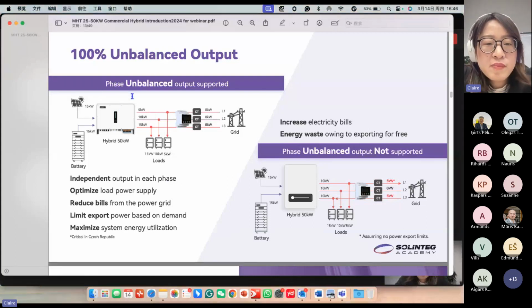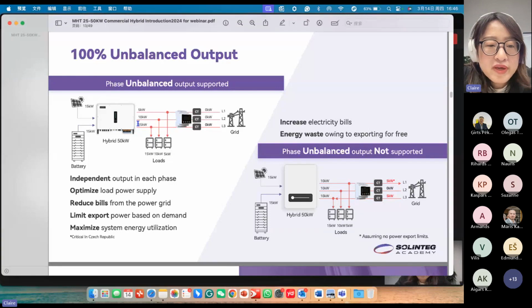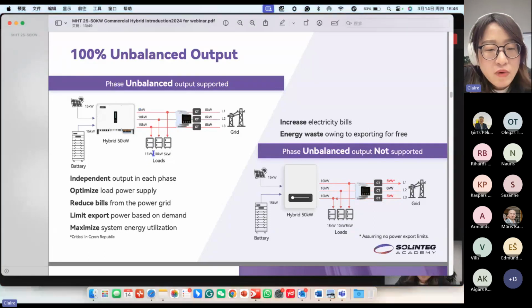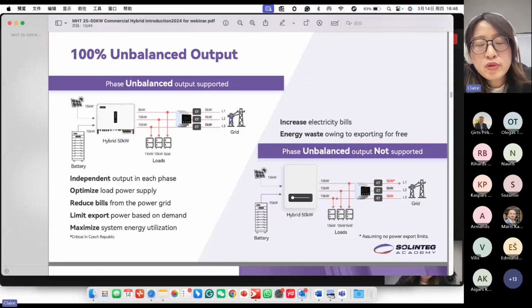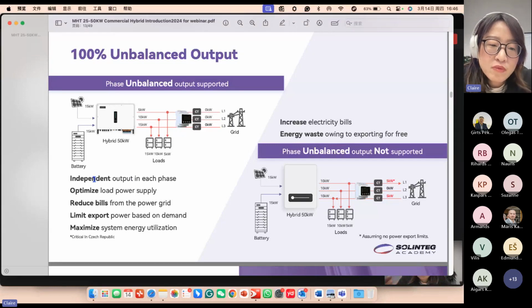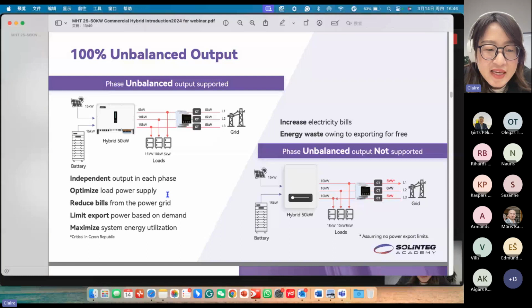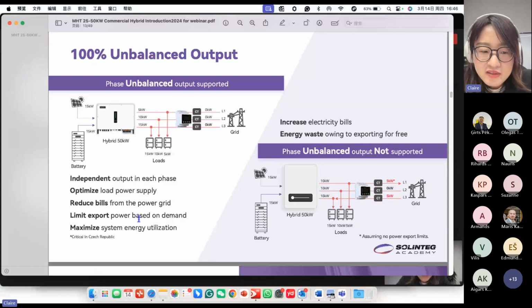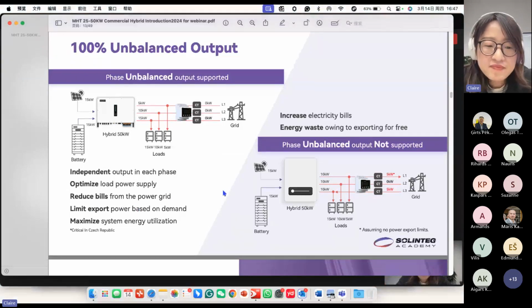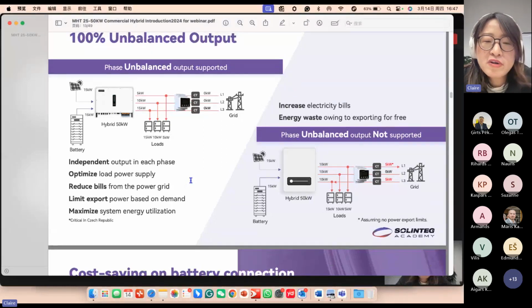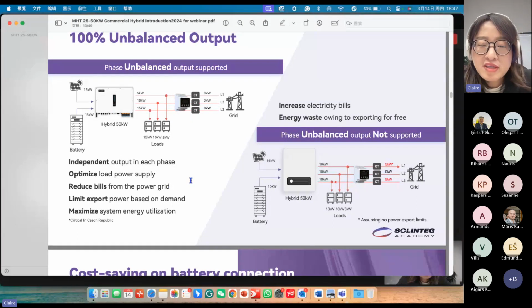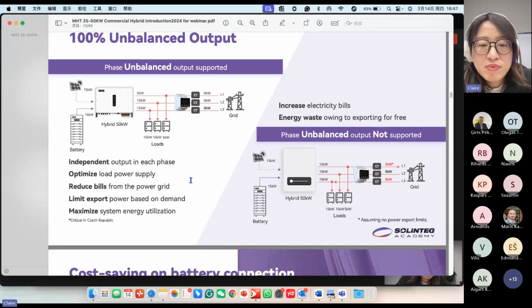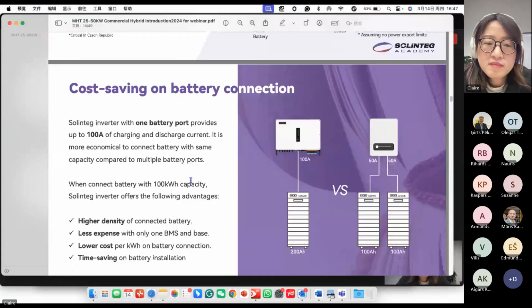And for Solinteg solution, we support unbalanced output. In the same situation, we can output exactly the power according to the load consumption. So in this case, we don't need to buy any power from the grid or sell any power to the grid. So we can optimize the load power supply and reduce the bills, and limit the export power based on the demand, and maximize the system utilization. This function is very useful in countries that measure each phase independently, like Czech Republic, also some Baltic countries.